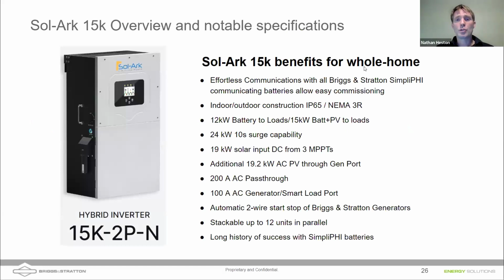So jumping into the Sol-Ark 15k, let's jump through the specs here quickly. First off, this is a 15k 2-phase, just meaning split phase. You get effortless communication with our batteries. Our batteries' BMS systems have long been designed to work seamlessly with Sol-Arks, and we continue to make sure that any firmware changes we make are approved and integrated with Sol-Ark so that you have seamless communication. The Sol-Ark 15k is an outdoor rated inverter. You can install this inside or outside. All of the hinges and components on this inverter are high quality stainless steel, and so it's IP65 NEMA 3R rated.